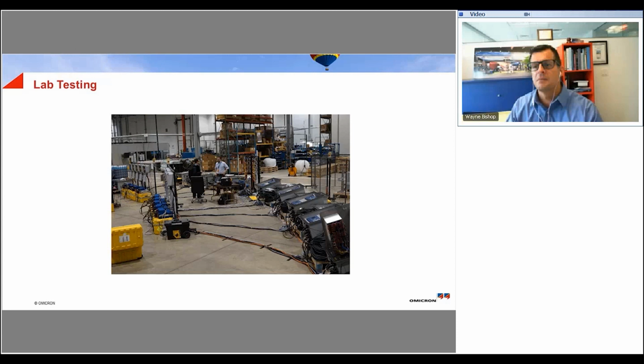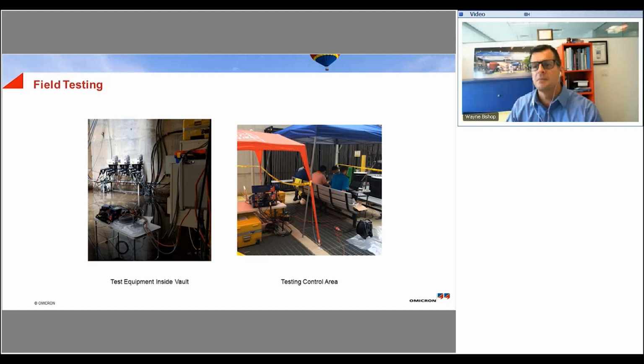Next, we can move on to the field test. For the field test, we implemented 10 different test sets to simulate all the primary pathways for all 9 of the underground vaults, as well as 1 of the individual load pathways. The testing techniques utilized centralized testing software, which was used to simulate the power system disturbances and distribute testing programs to all of the different test devices that were installed out in the field. The test set would then send all of the start times to all of the remote locations, and after all the tests were completed, would compile all of the test data for processing and analysis.